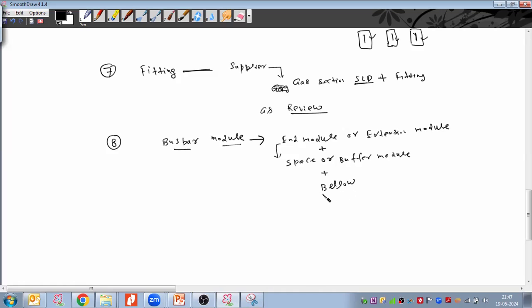This is not the model, but we take the bellow. Bellow is allowed when current is flowing in the conductors. When the current heats the busbar conductor, it expands, so this bellow allows the conductor adjustment at that moment. This is provided by the manufacturer for the conductor movement.